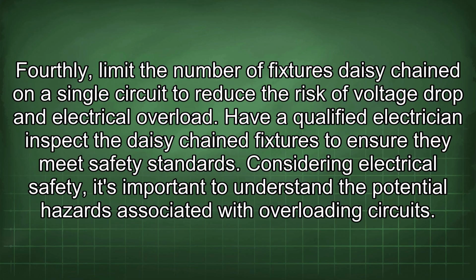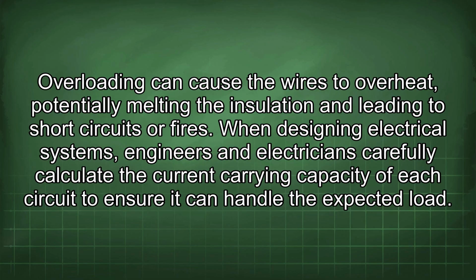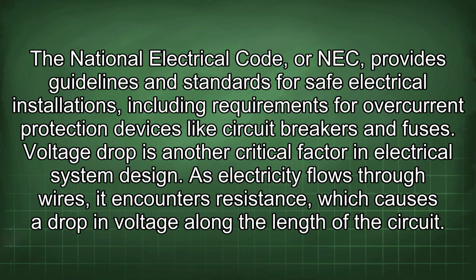Considering electrical safety, it's important to understand the potential hazards associated with overloading circuits. Overloading can cause the wires to overheat, potentially melting the insulation and leading to short circuits or fires. When designing electrical systems, engineers and electricians carefully calculate the current carrying capacity of each circuit to ensure it can handle the expected load. The National Electrical Code, or NEC, provides guidelines and standards for safe electrical installations, including requirements for overcurrent protection devices like circuit breakers and fuses.